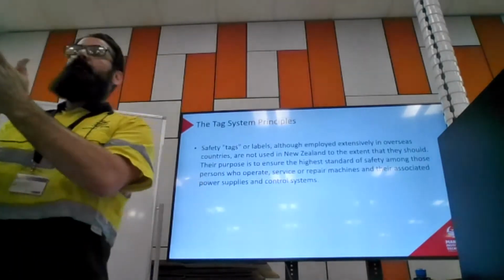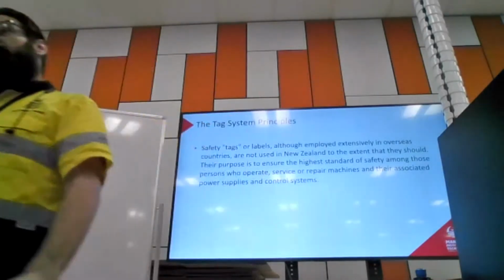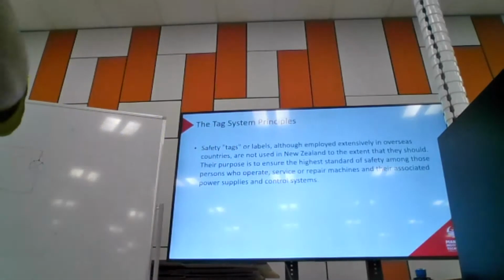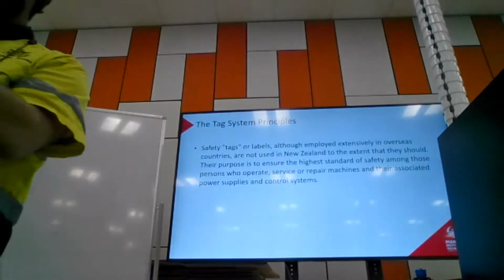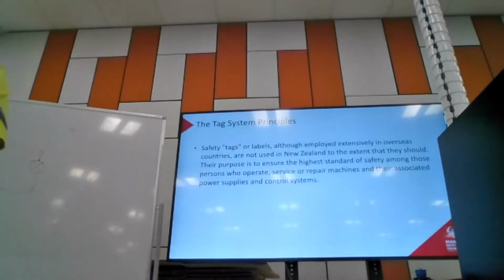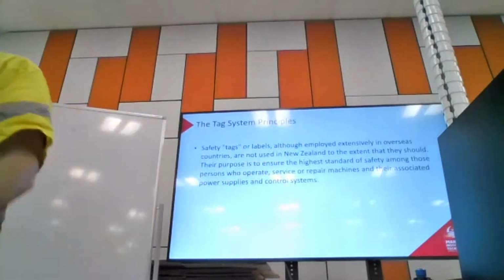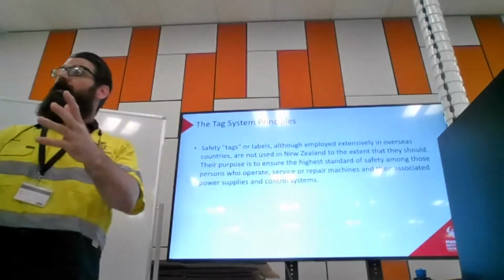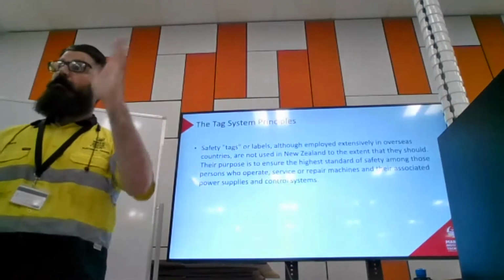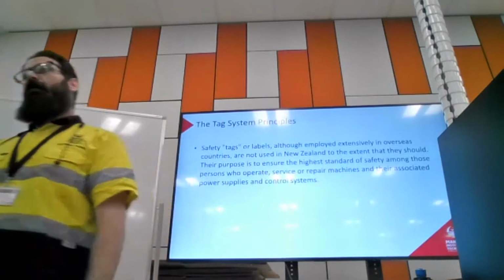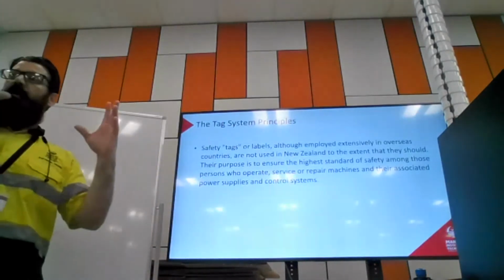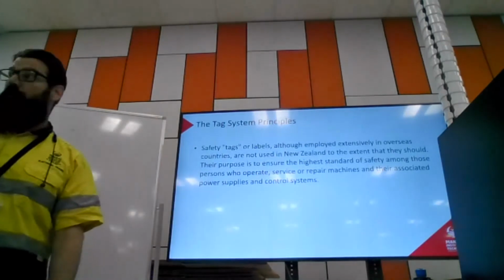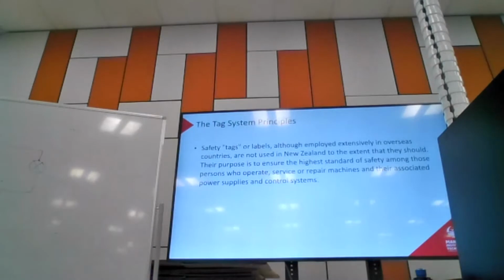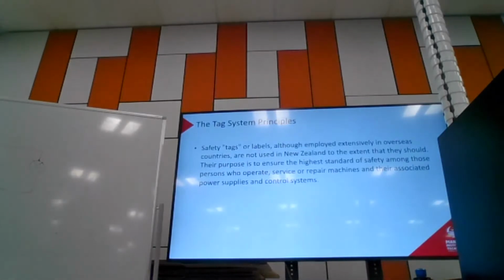What that means is whenever a new regulation comes into force, it does not apply to anything that already happened. So if they say every circuit in a domestic installation must be protected by an RCD, that means from the date of that regulation, anytime you put in a circuit, you must protect it with an RCD. It doesn't mean everyone has to go and rewire their house. It does mean that if I put a new circuit in an old house that doesn't have RCDs, I must put in an RCD for that circuit. But it never compels me to rebuild something that already existed, provided it was built and maintained under the laws at that time. So if I've got switches or circuit breakers that aren't lockable because they're older, there's no requirement for those to be changed.